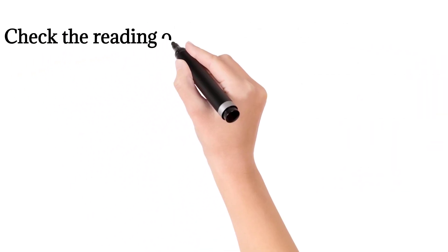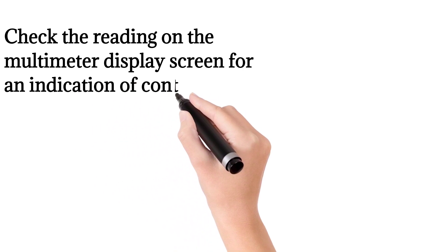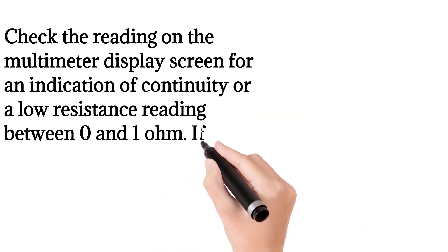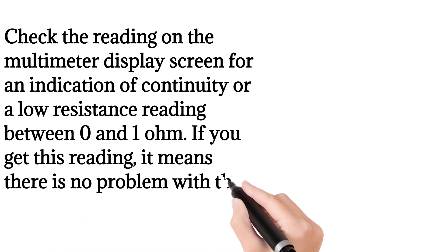Check the reading on the multimeter display screen for an indication of continuity or a low resistance reading between zero and one ohm. If you get this reading, it means there is no problem with the solenoid.